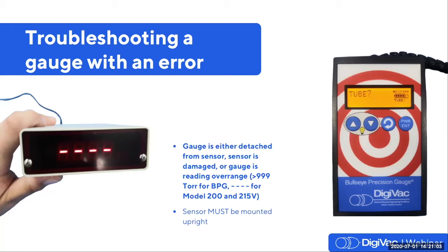For the Bullseye Precision Gauge, we clamp the readings at 999,000 microns or 999 torr. So any indicated pressure above that range will cause the gauge to display this error message. These conditions also exist to cause the dashes on the Model 200. So we use the same principles to test the sensor on those gauges as well.